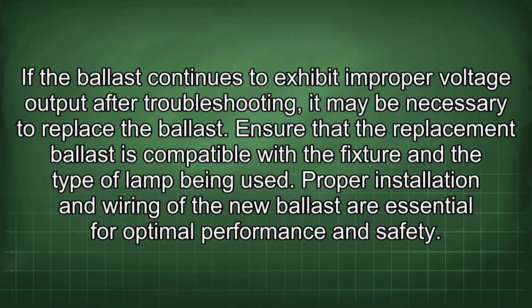If the ballast continues to exhibit improper voltage output after troubleshooting, it may be necessary to replace the ballast. Ensure that the replacement ballast is compatible with the fixture and the type of lamp being used. Proper installation and wiring of the new ballast are essential for optimal performance and safety.